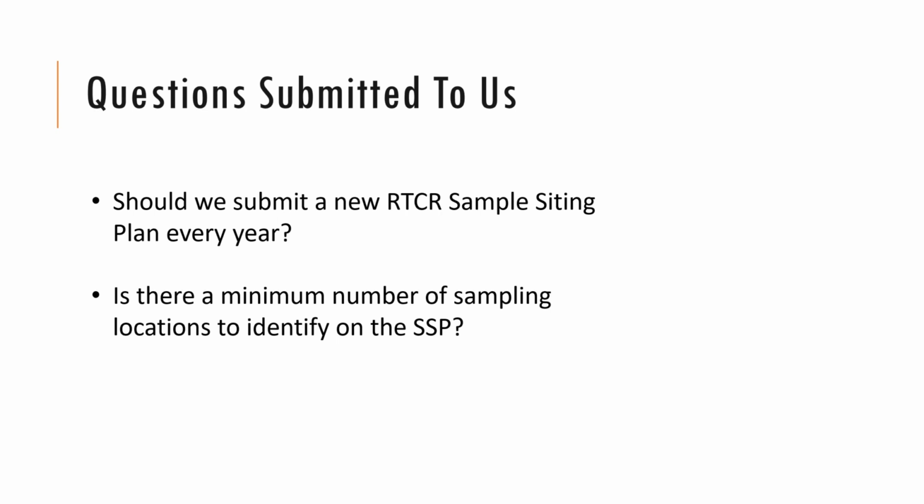And for your repeat sampling, you'll have to have 3 locations. One will be the original location, one which will be 5 connections upstream, another 5 connections downstream. So that'll be 3 sampling locations total. But again, for example, New Jersey DEP, on their sampling site plan recommendation, I think they said double: for every required sample they take, they should have additional monitoring locations. So if you're required to take 1 routine sample, you should probably have 2 sample sites that you can take samples from.